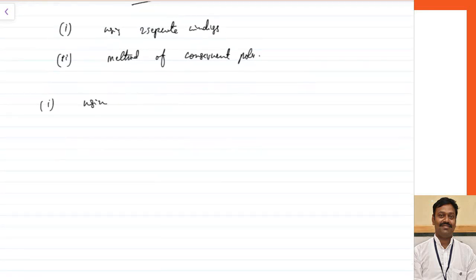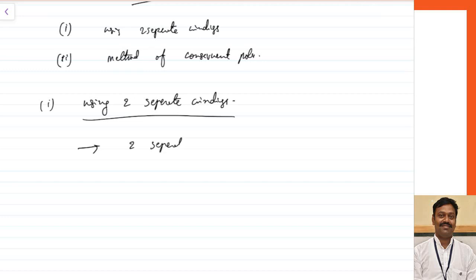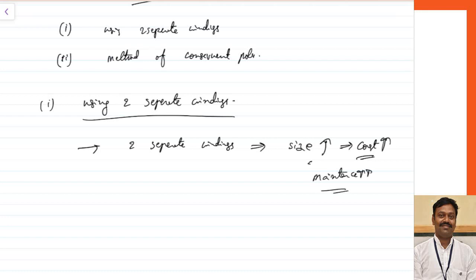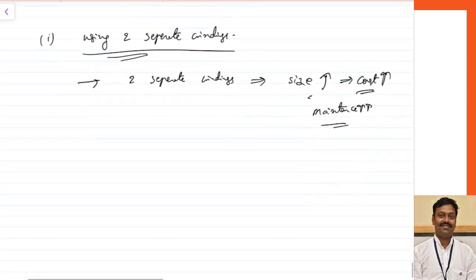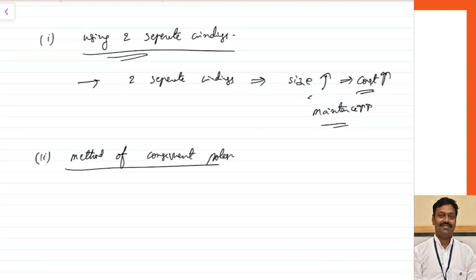Using two separate windings means in the stator you need two windings. When two separate windings are required, the size of your stator increases, and when size increases, cost increases. Obviously when the windings are more, maintenance also increases. That is why this method is not used in practice — keeping two separate windings is a very costly affair, very difficult, and has high maintenance. That is why practically we always go for the method of consequent poles.